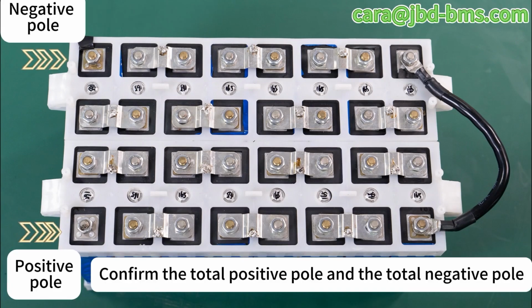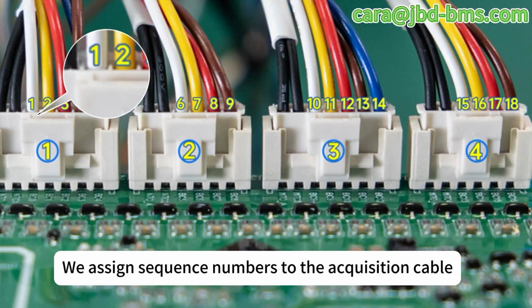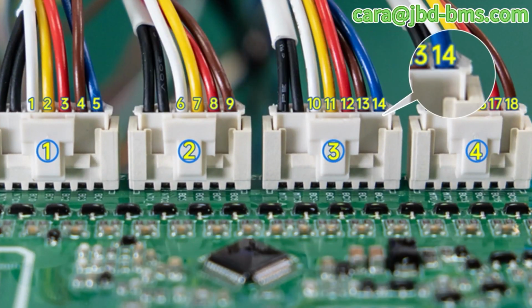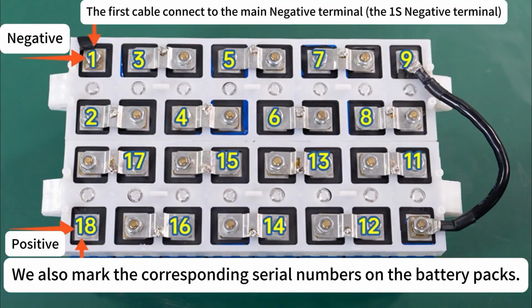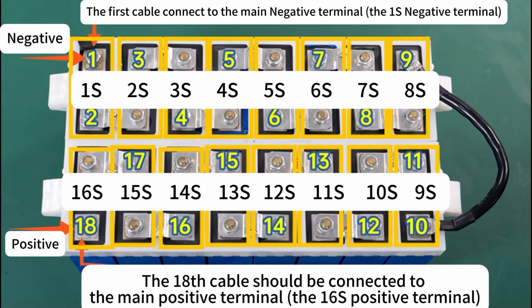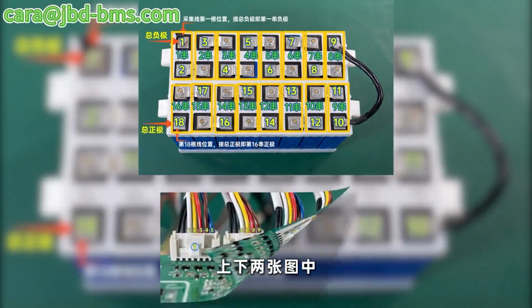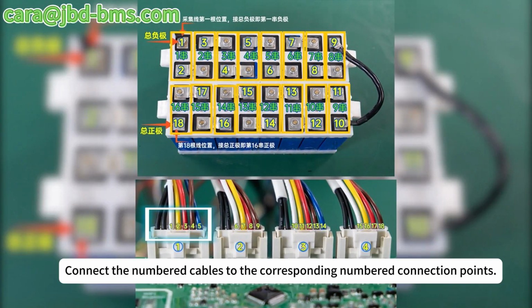Before connection, confirm the total positive pole and the total negative pole. After confirmation, assign sequence numbers to the acquisition cables, and mark the corresponding serial numbers on the battery packs. The 18th cable should be connected to the main positive terminal. In the 2 images above and below, connect the numbered cables to the corresponding numbered connection points.